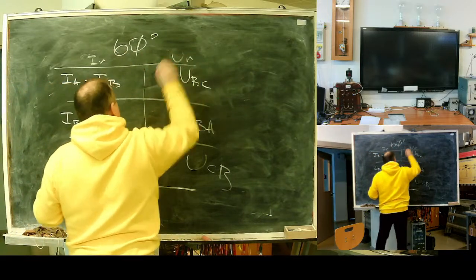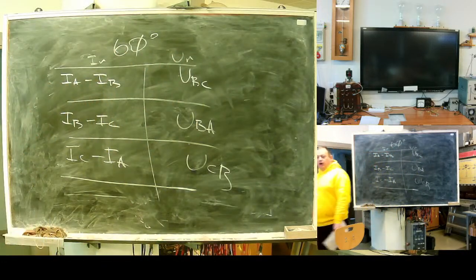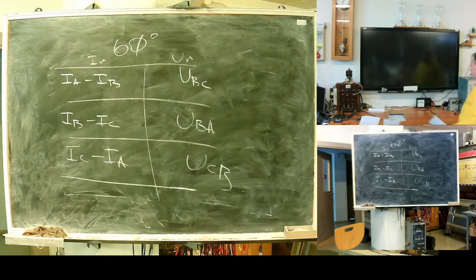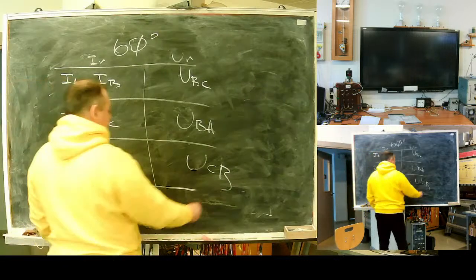Current voltage. What can you tell about this? On the one hand, in case of three-phase fault, it's more sensitive because the difference of current will produce square root of 3. In line-to-line, for two-phase fault, it operates. But there is one tiny problem.